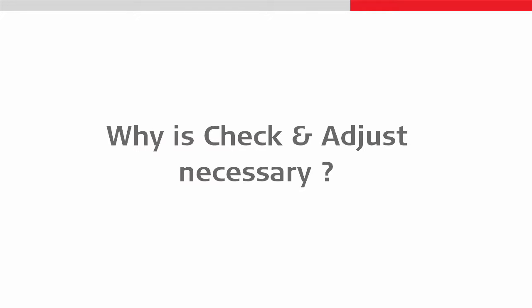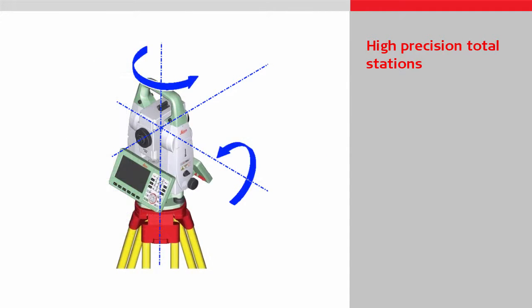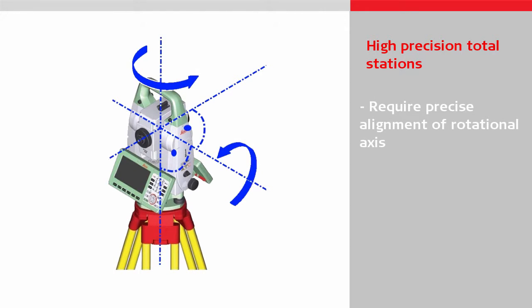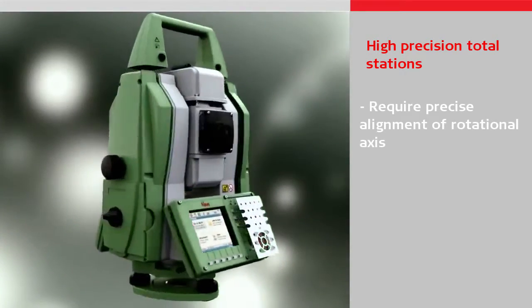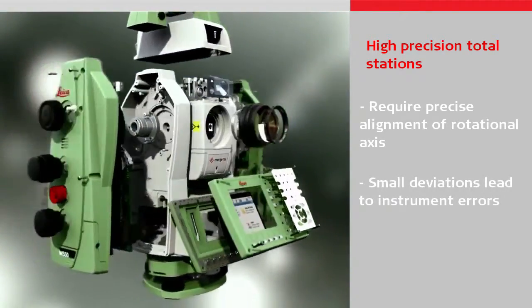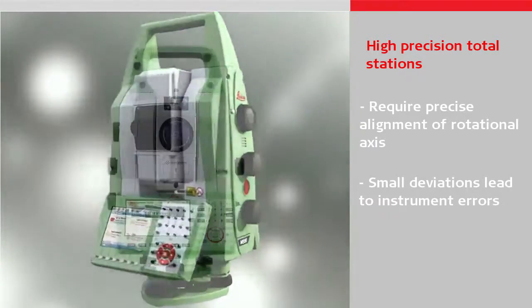Basically, the check and adjust feature is a tool to do a user calibration of the instrument. To measure with high precision, total stations have to fulfill specific requirements of the rotational axis, in particular regarding the alignment of those axes. Meeting these requirements is a tough task during manufacturing. Even the most careful and precise assembly process will result in small deviations which can lead to so-called instrument errors.